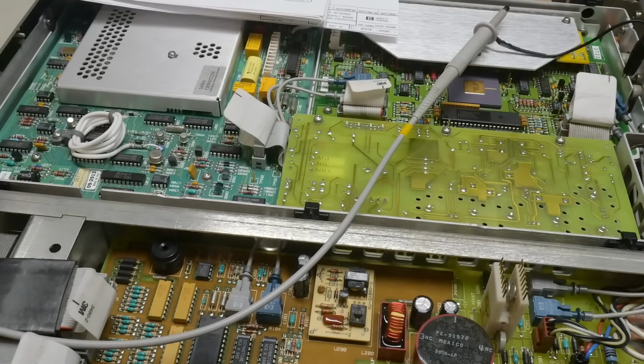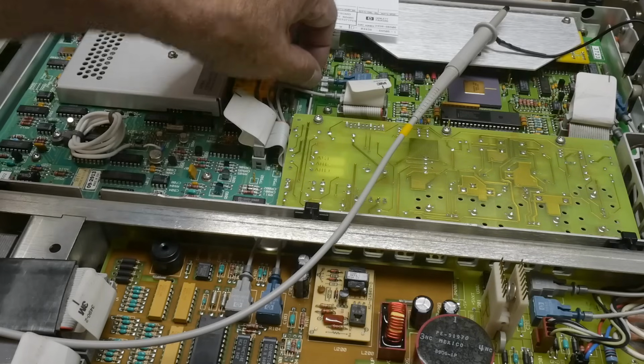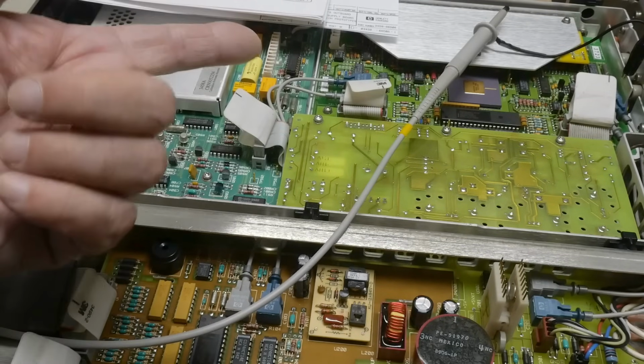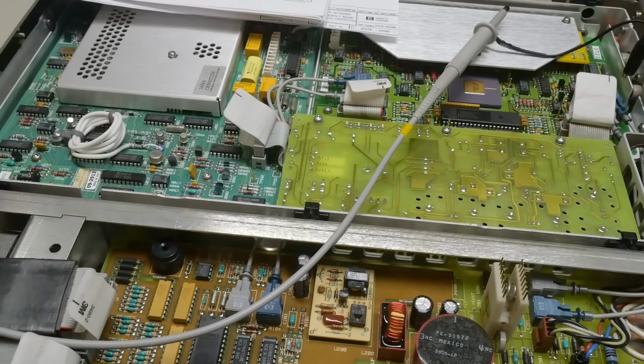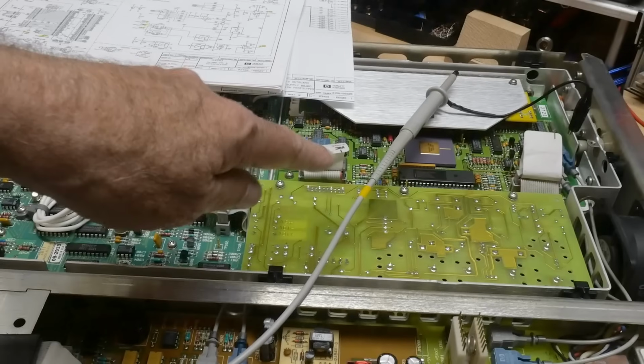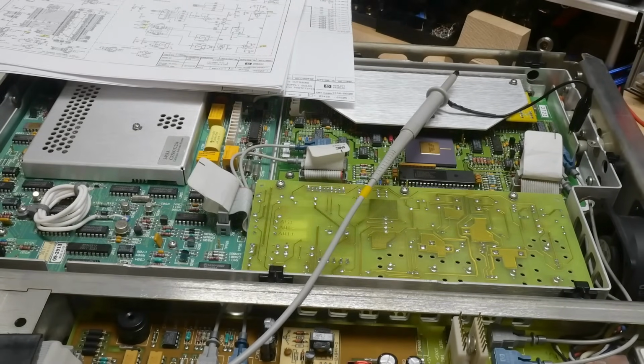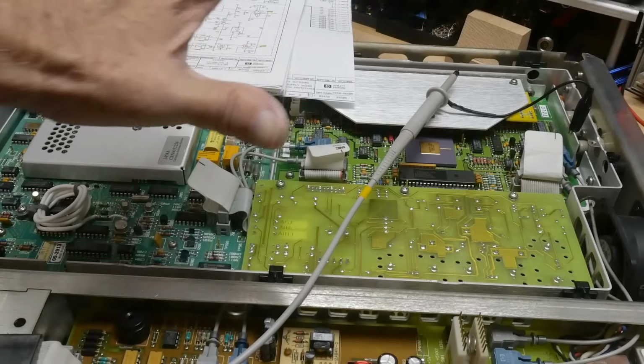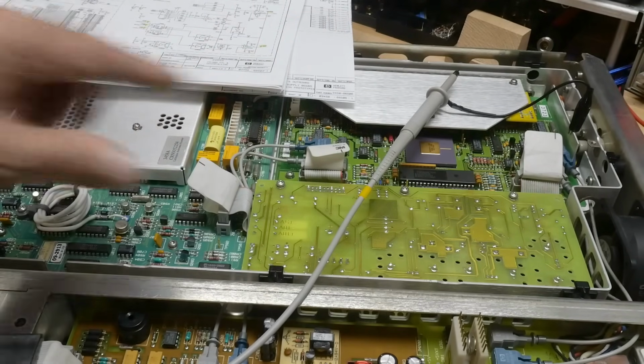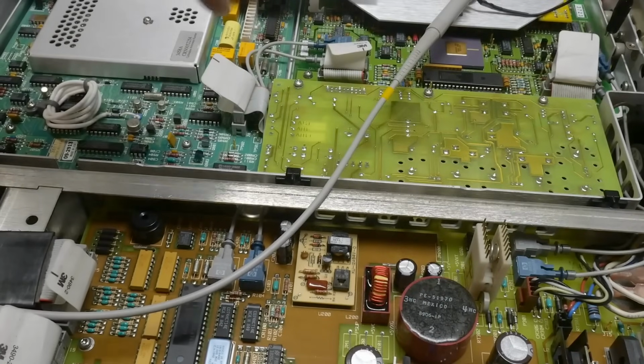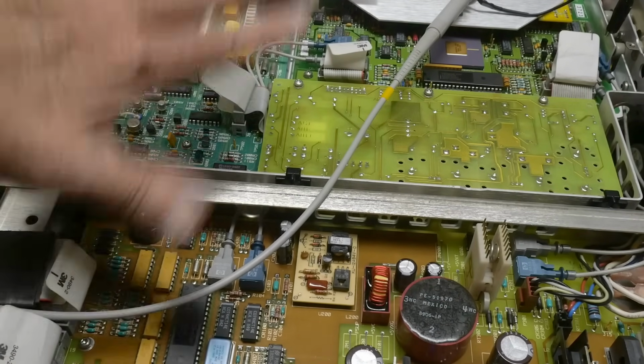And I know it does somewhat, because if you unplug one of these cables, it goes bad. And I also know it's working because if you can hear this, you hear the click? There's a beep, but there's also a click. And that is that this board is commanding that board, actually the board underneath it, to close a relay. So I know that transmit from here and receive over there is working right. Okay. What I don't know is if transmit here gets to receive here. So that's the one we got to test today.